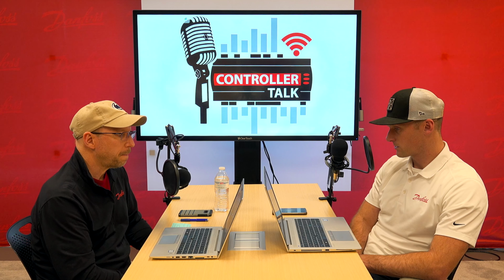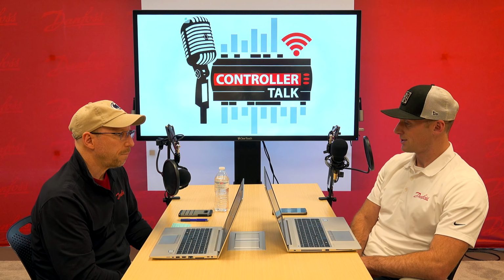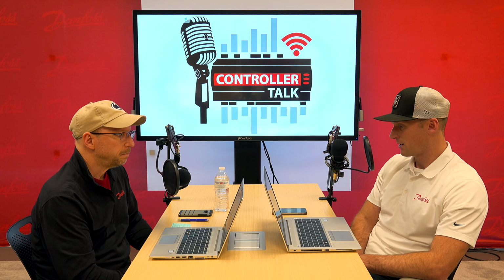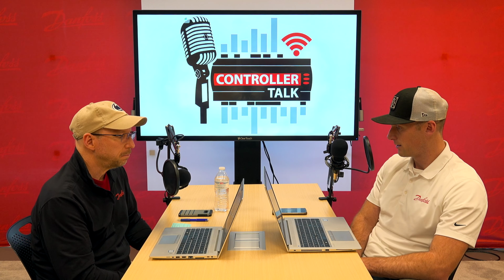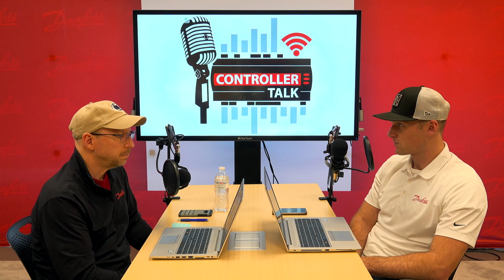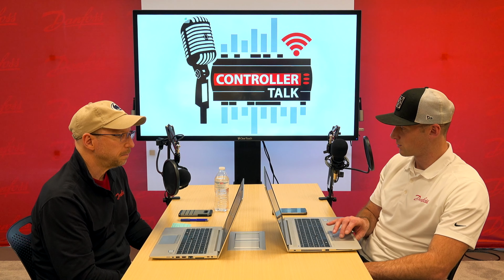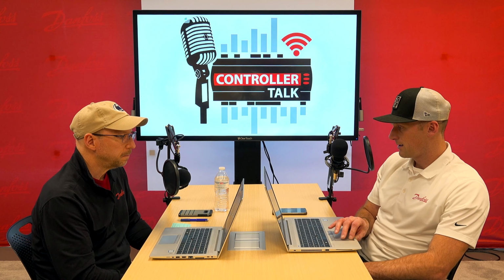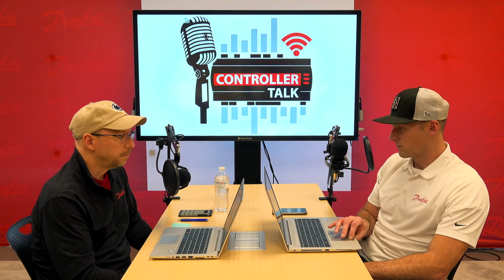And then there's settings for your superheat, kind of sticking with that same theme where you limit min and max. People can dial this in to their own desire, I guess you could say, from one customer to the next. But I'd say across the board, a general starting point that we see with CO2 is a minimum of 10 and a maximum of 15 degree Fahrenheit for your superheat settings. So we're trying to stay within that range when we're controlling an evaporator with a case controller for a CO2 system.